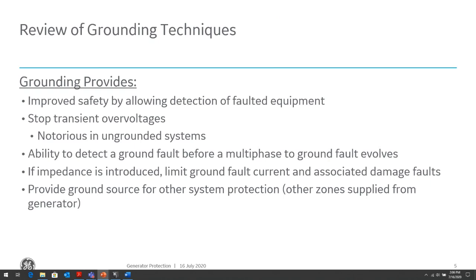Ability to detect the ground fault before it evolves into a multi-phase fault is very important, because as we know, multi-phase faults can cause large amounts of fault current to flow in the protective equipment and not only cause permanent damage to that equipment, but maybe collateral damage to the surrounding equipment. The strategy to limit ground fault current and hence potential for damage is proper grounding, whether it's low impedance or high impedance, and we'll talk about both of those types of grounding that are common.